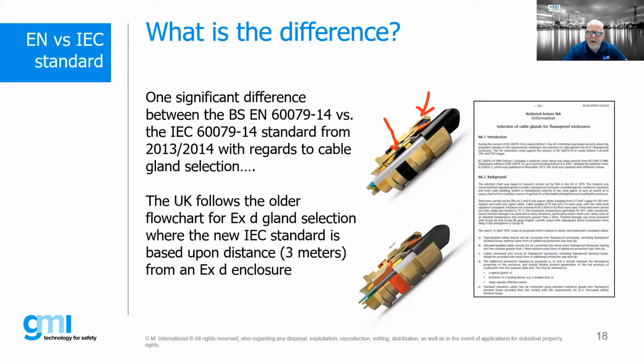The difference is down here at the bottom, you see there's actually a compound material. This is a hardened compound that becomes very hard, and it's a permanent installation. Once that gets packed or poured, that is permanent. You can disassemble the gland, but if you had to re-pull or do something different with your cable, you'd have to cut it off and start anew. So that's considered to be a barrier gland, marked B, and this is NB, non-barrier, down here.